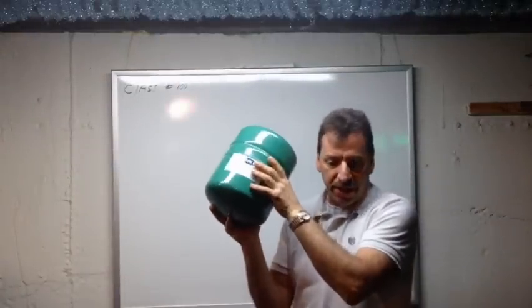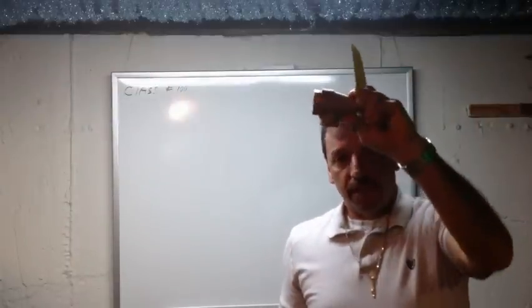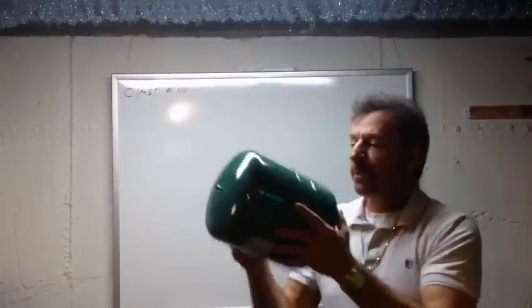That's how you know it's the expansion tank. So you have the relief valve, the pressure relief valve itself, or the expansion tank, which causes the relief valve to go bad.